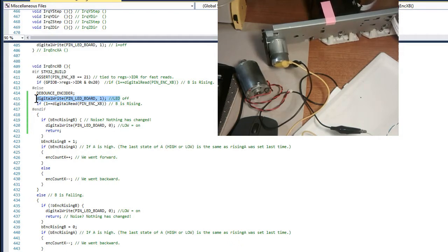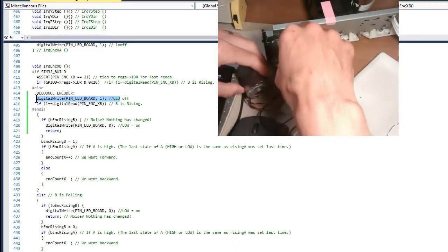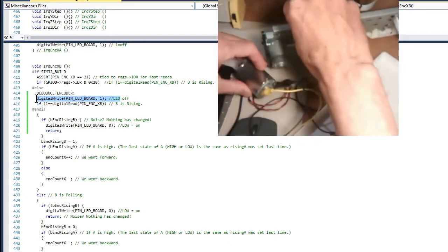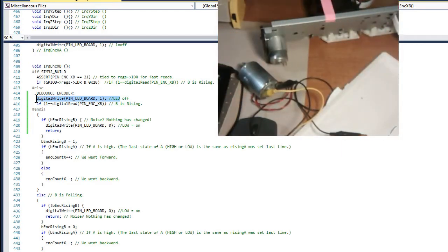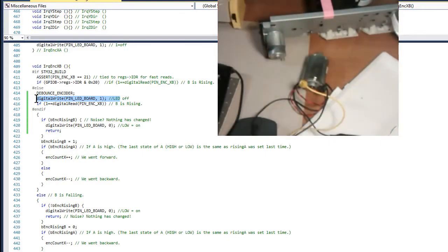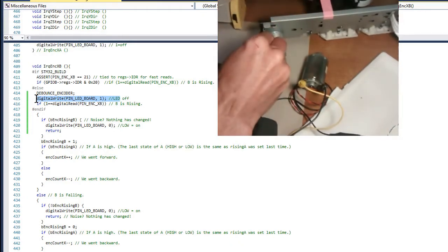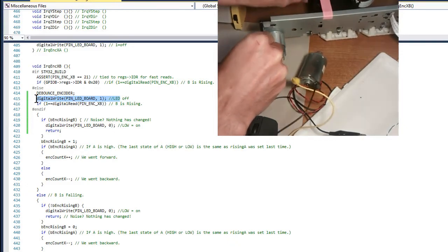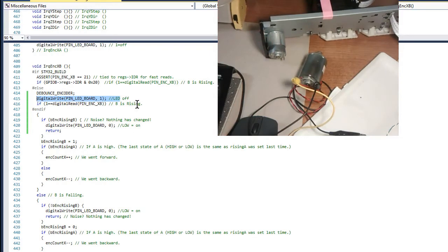So now let me turn this off for a second and reconnect this other motor. I won't get that light turning on anymore. Now the motor's turning, but it's not turning back and forth like the other one because the optical encoder is connected to the shuttle. So I have to manually move it, and then you can see the torque is changing direction on the motor. But when I'm doing this, I'm not noticing that light turn on, so that means I'm not getting into this noise condition where it's detected a rising pulse when it's already risen.